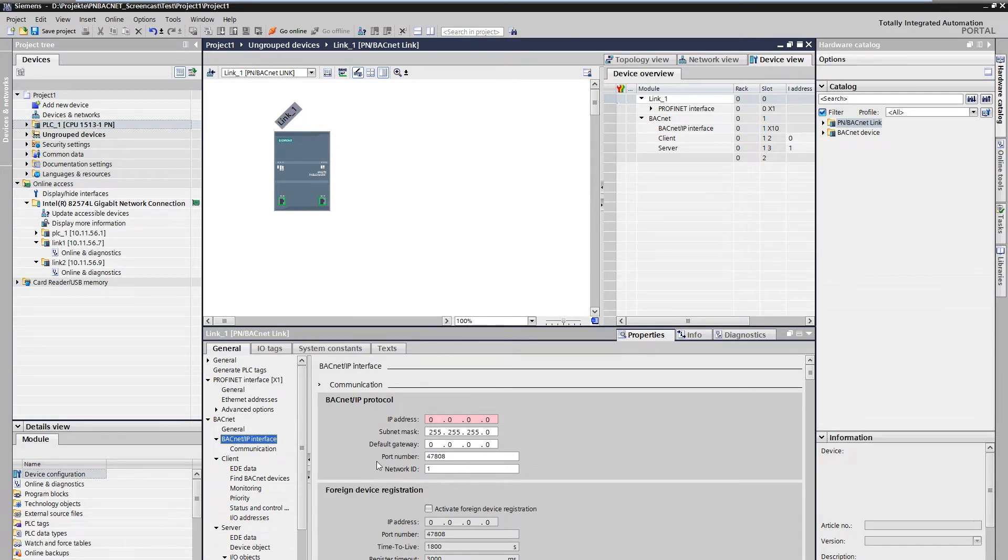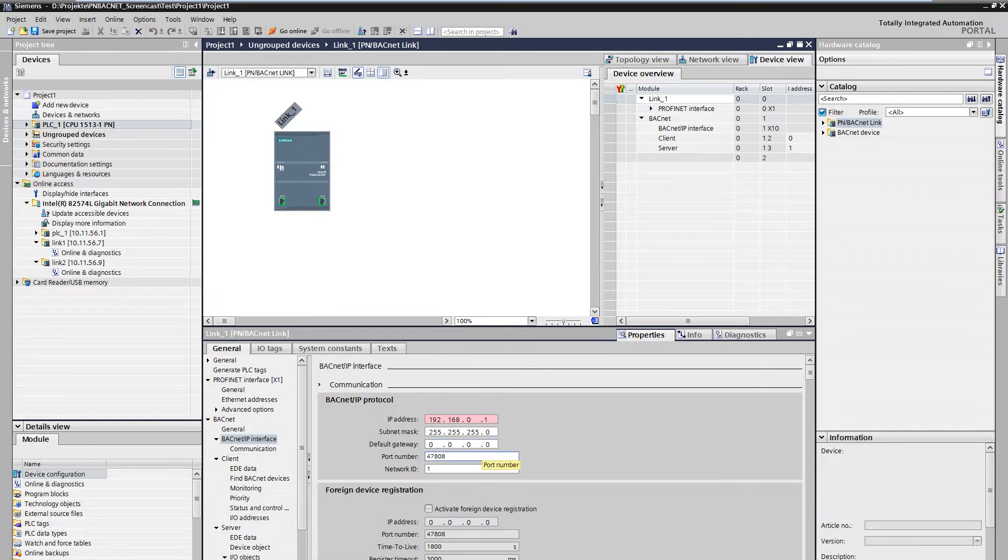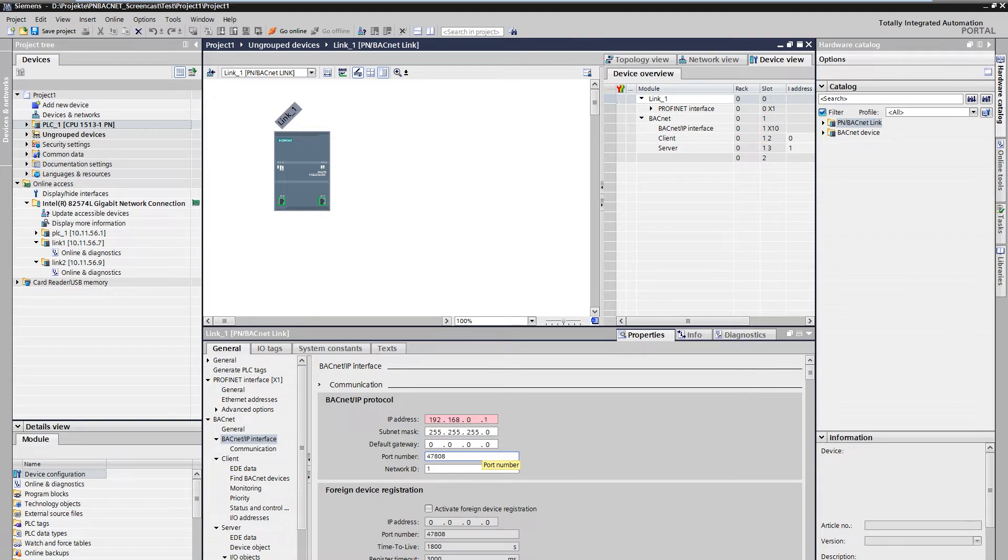This address must be unique in the network. A default gateway can be defined since the telegrams are routable. The port number is used for communication and is valid for server and client. Port 47808 is the standard BACnet port. The network ID is the explicit ID of the BACnet network.